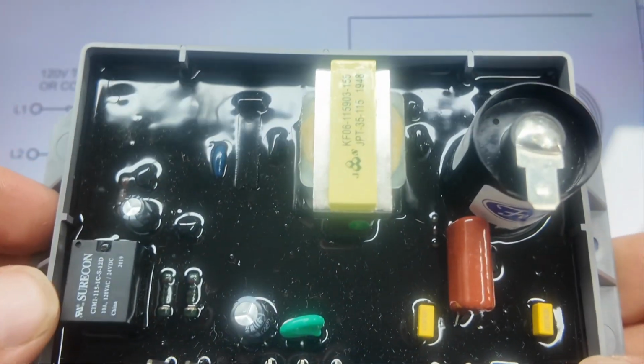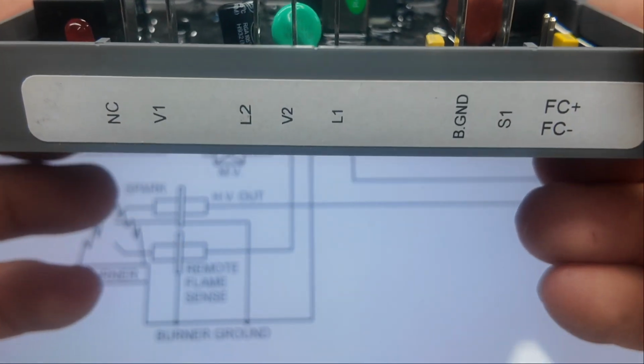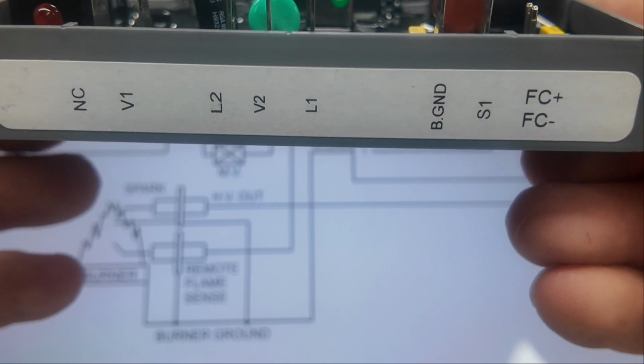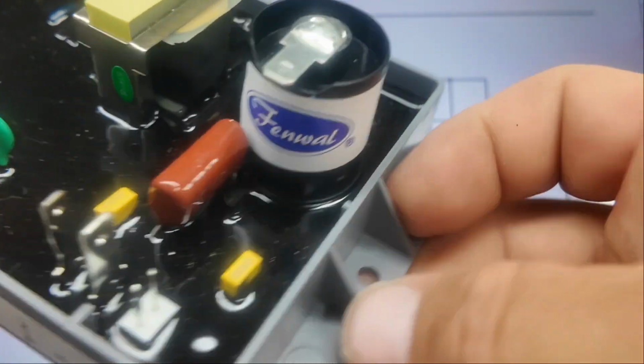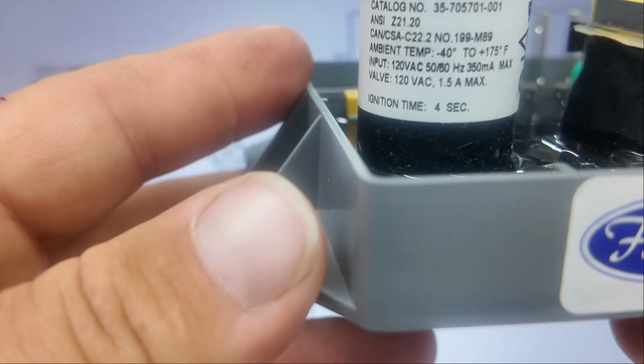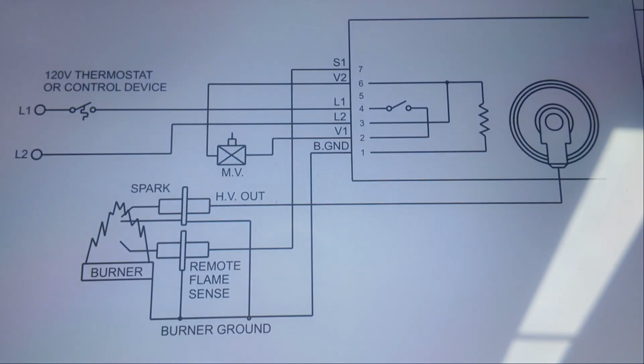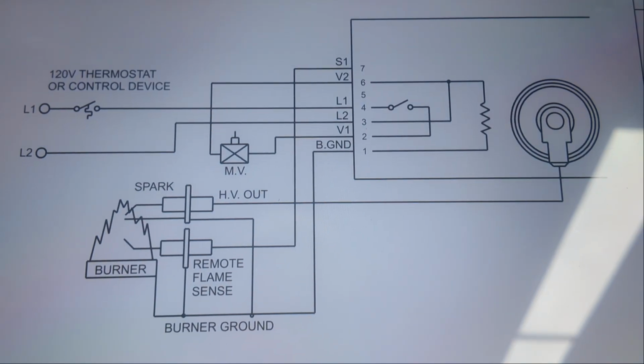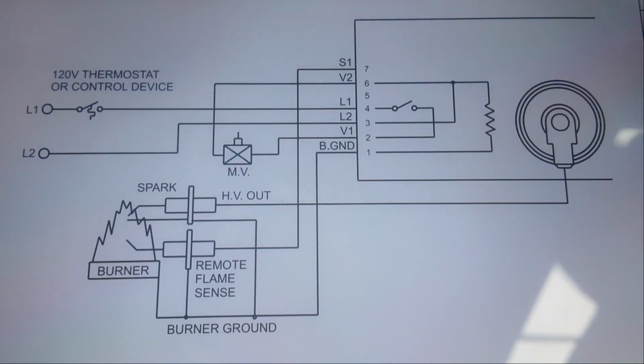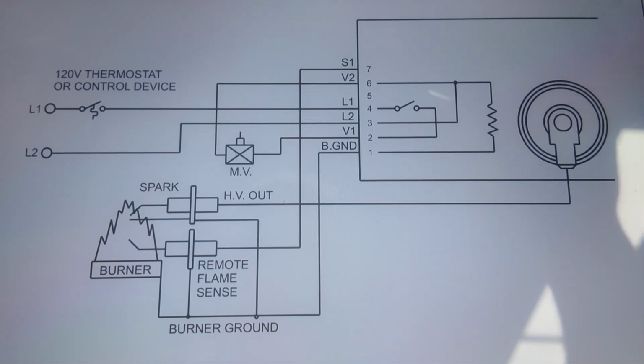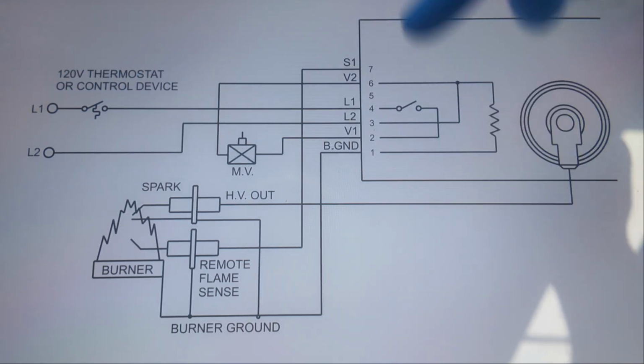They're a very simple board, and some people use them at times to replace other brands of boards. That's about all there is to it. They're a very simple board. I've used them with anywhere from 4 to 30 seconds for your purge time, depending on the burner or depending on the application. And that right there is the wiring diagram that you need to look at, because that's how things need to be wired.